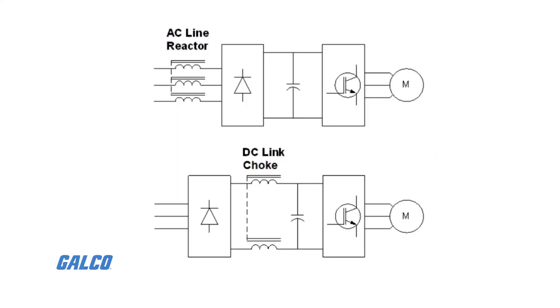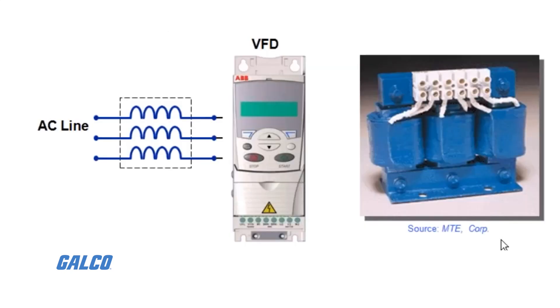With some types of variable speed drives, like DC and current source inverters, it may be necessary to add an isolation transformer or AC line reactors between the source and drive to prevent interference with other electrical equipment.